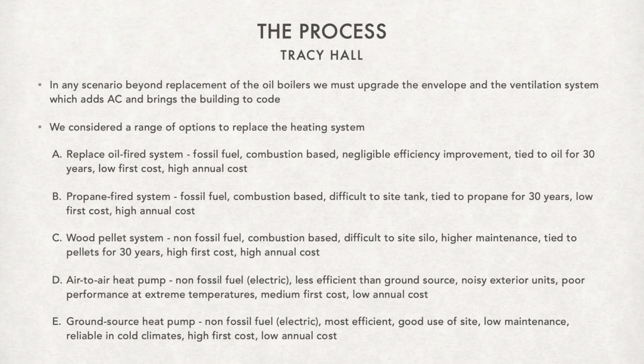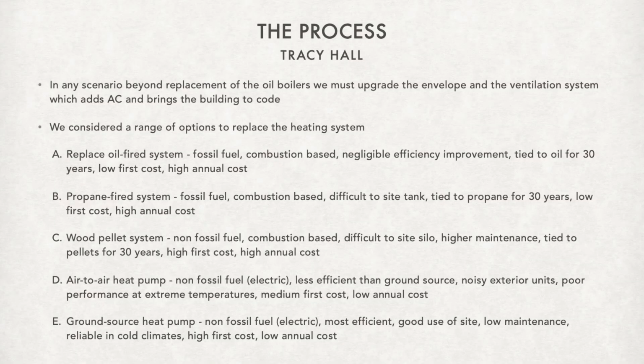We talked about a wood pellet system. It's not strictly speaking a fossil fuel, but it is a combustion fuel, so that's not ideal. Like the propane tank, there's not really any obvious place to put a silo for pellets. It's the same problem—you probably have to take some parking places, or if you put it on the exterior, take away some office space on the interior. A wood pellet system is arguably higher maintenance than other systems, and again we're tied to that particular fuel for 30 years. It has a relatively high first cost, not maybe the highest on our list, but higher than probably propane or oil. And it has a fuel cost, same as propane and oil.